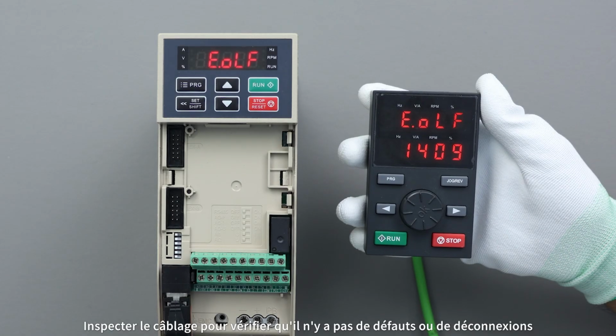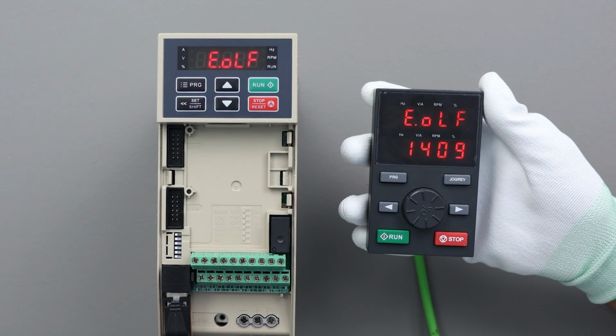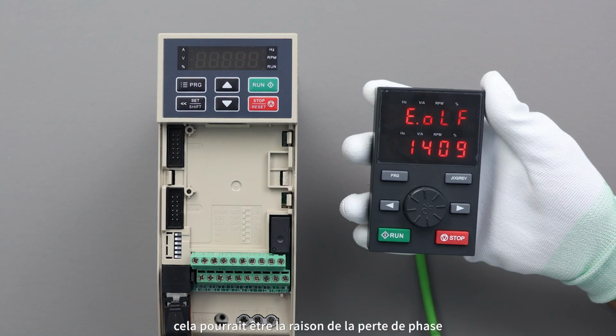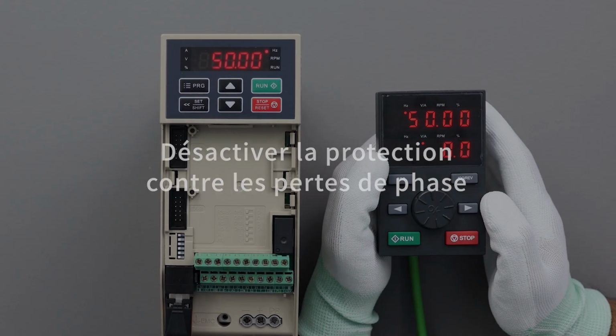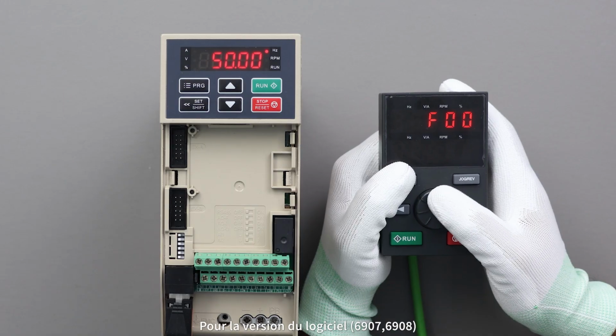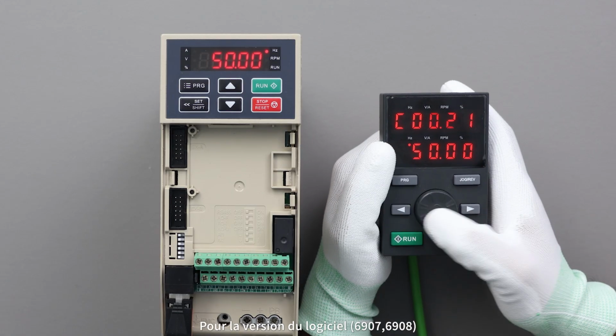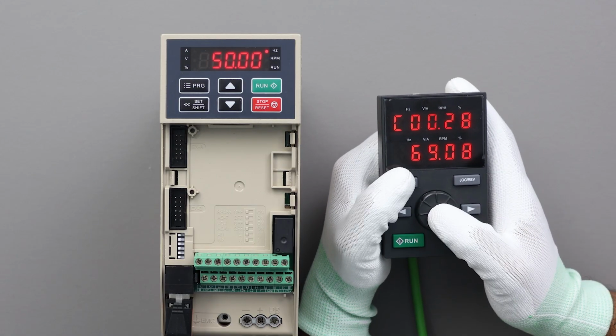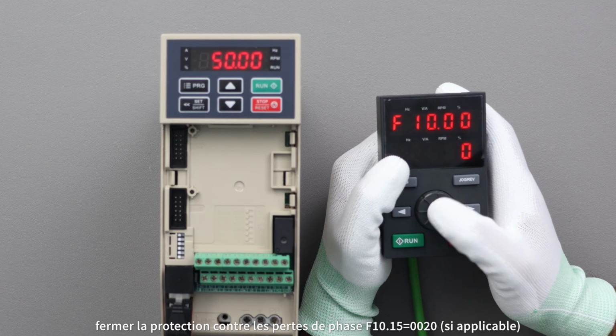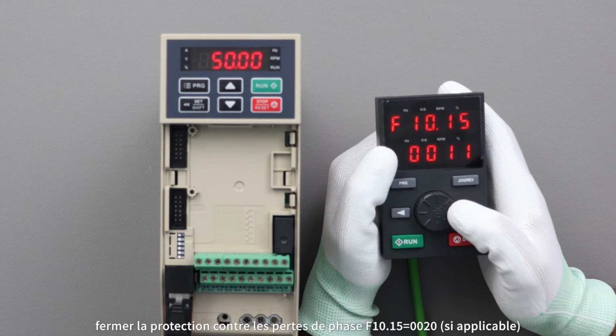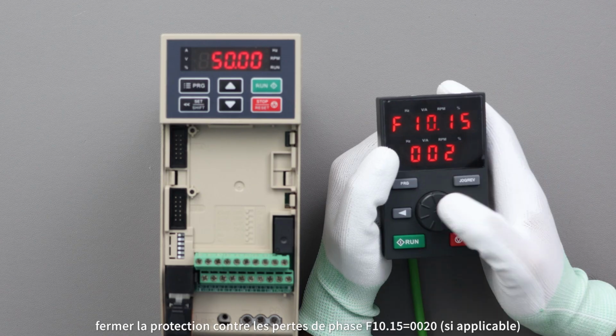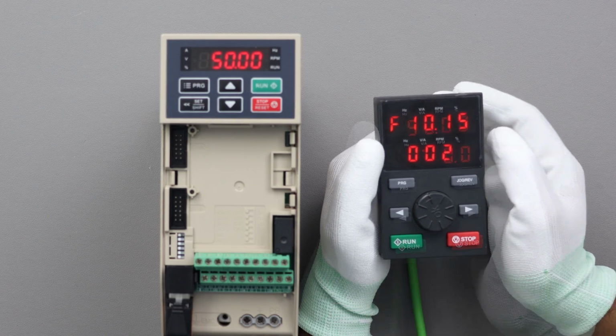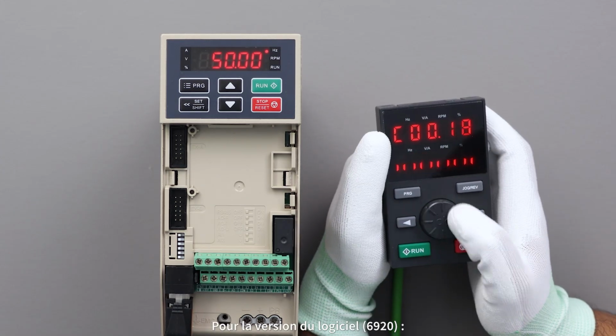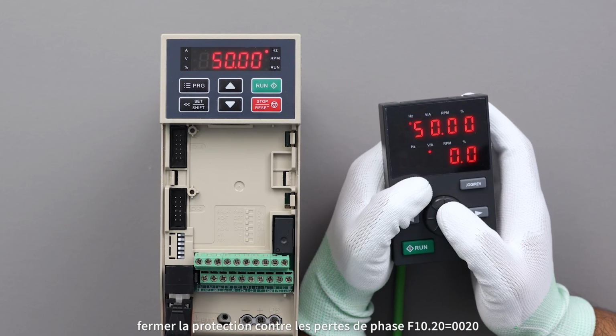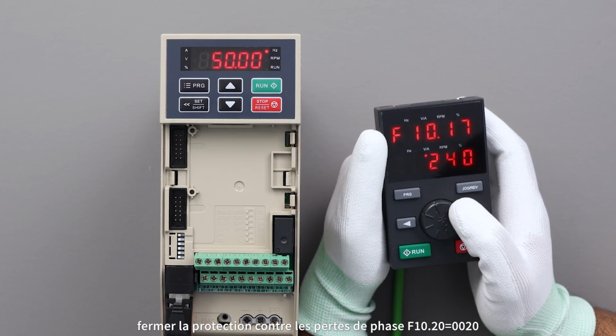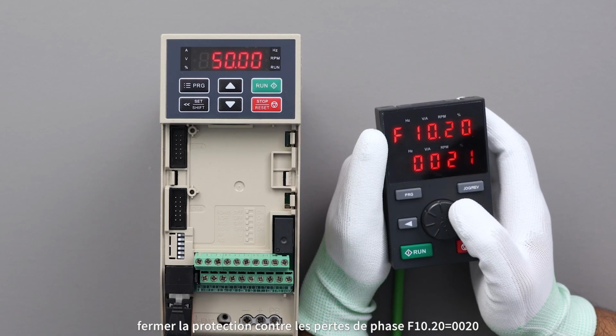Inspect the wiring for any faults or disconnection that could be the reason for phase loss. Turn off phase loss protection. For software version 6907 and 6908, close phase loss protection F10.15 to set 0020. For software version 6920, close phase loss protection F10.20 to 0020.